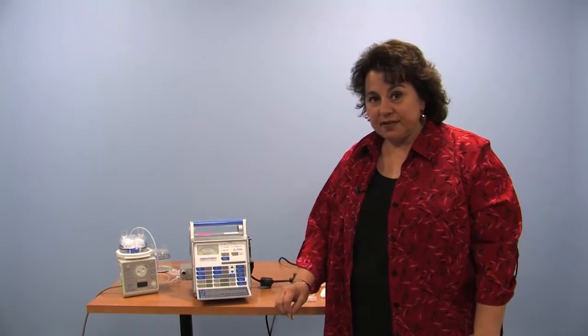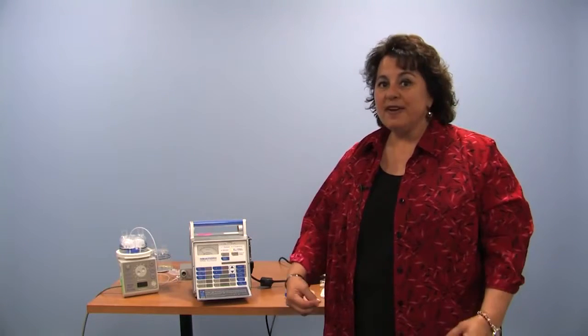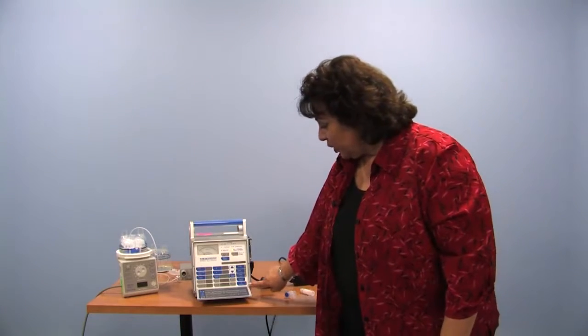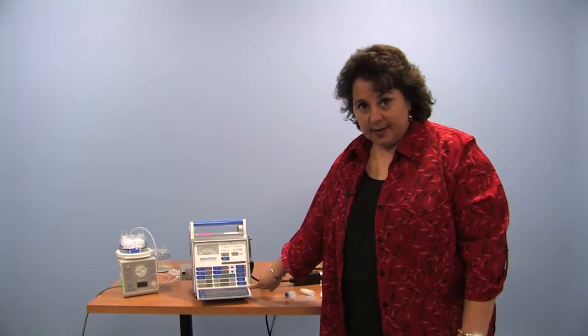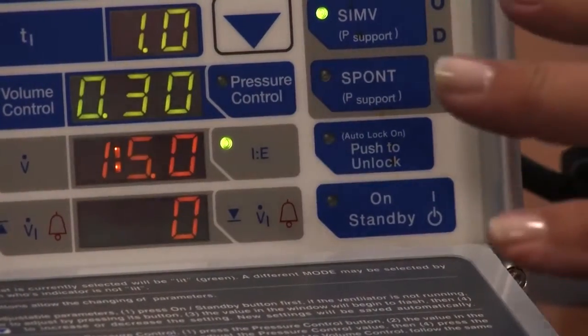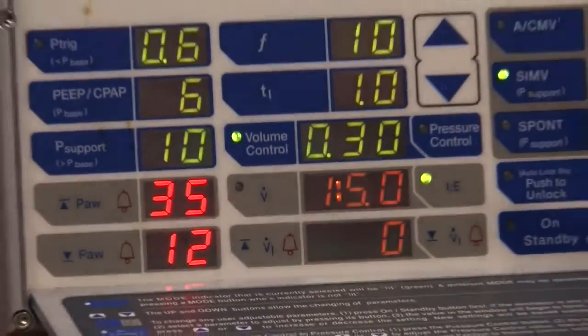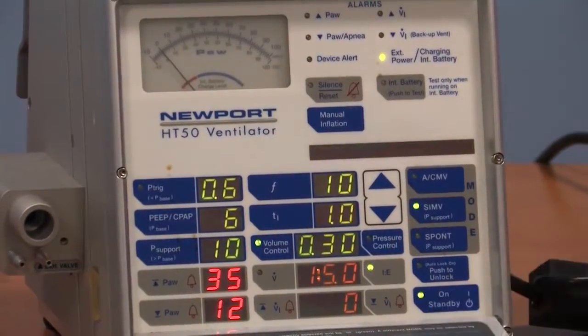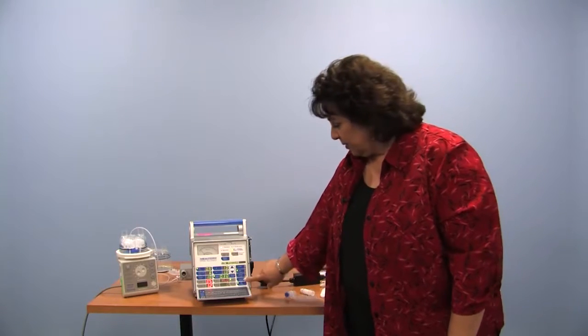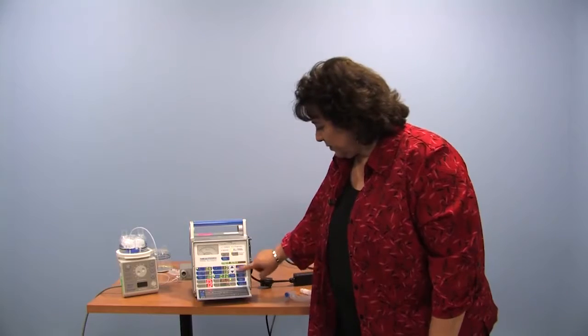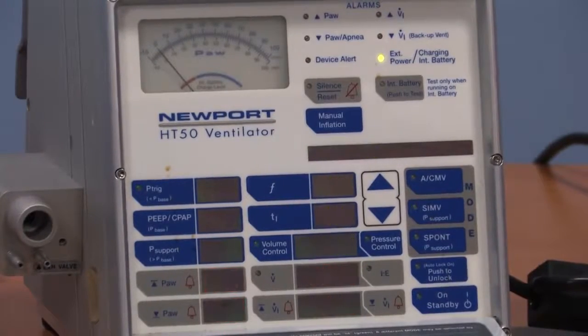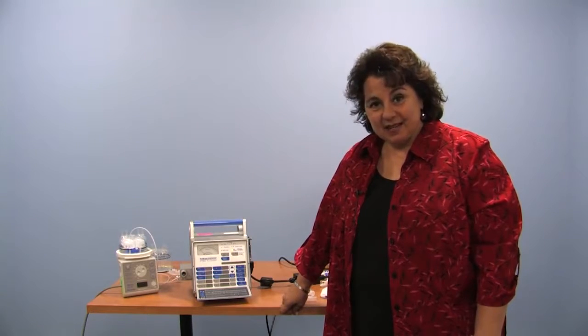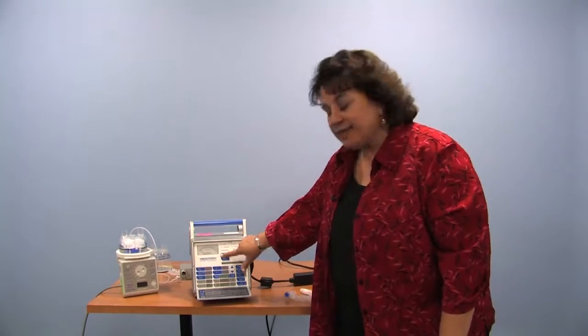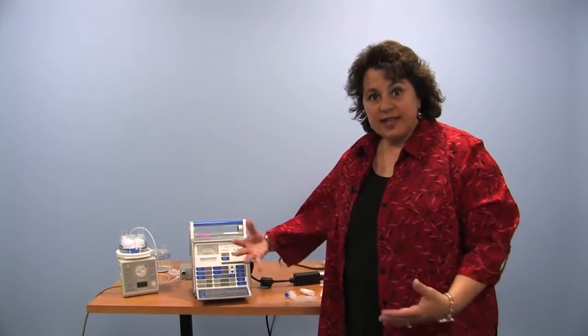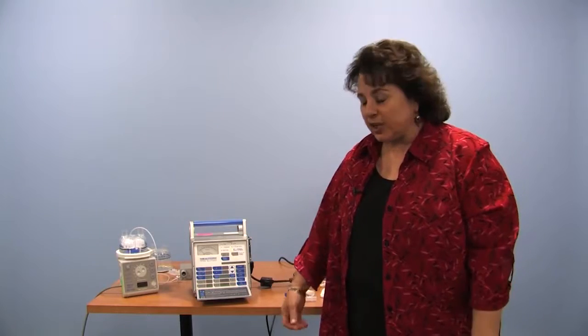The most important take-home message today about the Newport HT50 ventilator is that to turn it on to ventilate your child, you must push the on standby button twice. You hit it once to view the settings, assure they're appropriate and/or adjust them, and twice to enable ventilation. To turn it off, again, twice to turn it off. And then you must silence the alarm so the ventilator understands that a human being has seen that it's been taken off a person.